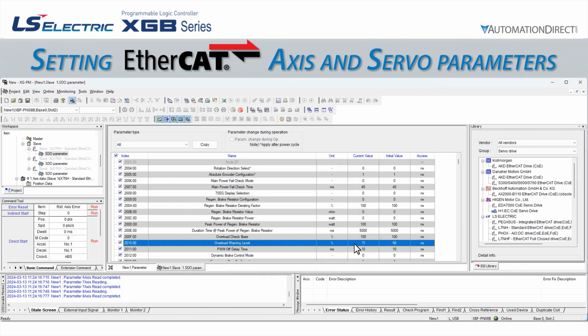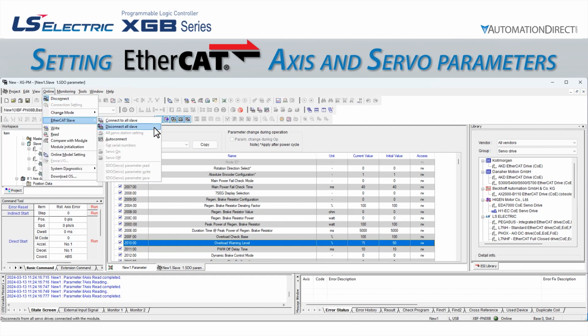We have now changed the parameter in the software, but it isn't on the drive yet. Remember that a normal write to the CPU includes axis parameters, but it does not include SDO parameters. For this function, we have to perform an SDO servo parameter write. We will find this option under Online EtherCAT Slave. In our case, it is currently grayed out. That is because we haven't connected the EtherCAT network, so we aren't communicating with any of the slaves yet.